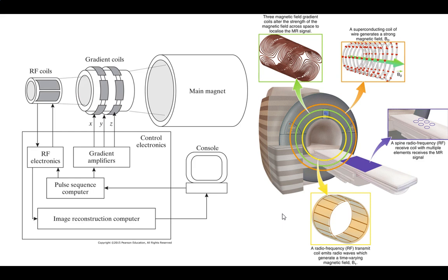I tried to give you a couple of these that gave some general ideas. The outside one is a really big coil, a single wire that's wrapped all the way down. It's usually pretty stupid thick. And that's the one we really care about when we're liquid cooling, because you need that main field to be crazy stable and linear. All the other stuff, you're going to be adjusting how much you want it, the gradients on it, to be able to create an effect.